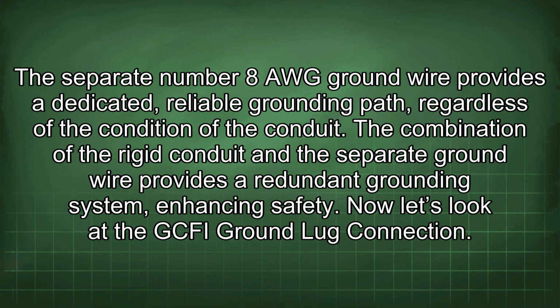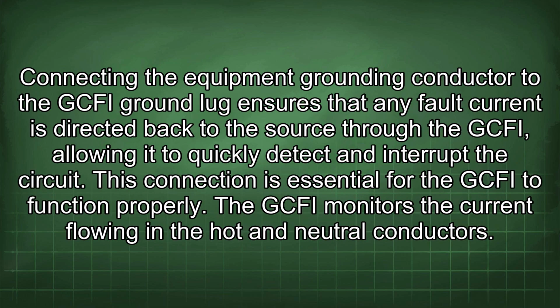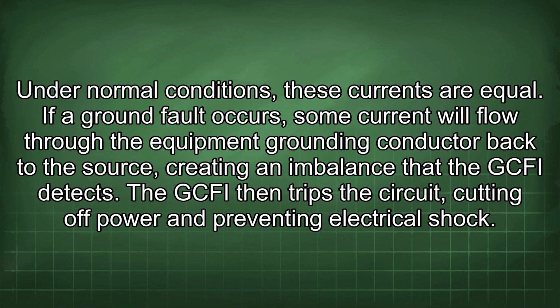Now let's look at the GFCI ground lug connection. Connecting the equipment grounding conductor to the GFCI ground lug ensures that any fault current is directed back to the source through the GFCI, allowing it to quickly detect and interrupt the circuit. This connection is essential for the GFCI to function properly. The GFCI monitors the current flowing in the hot and neutral conductors. Under normal conditions, these currents are equal.